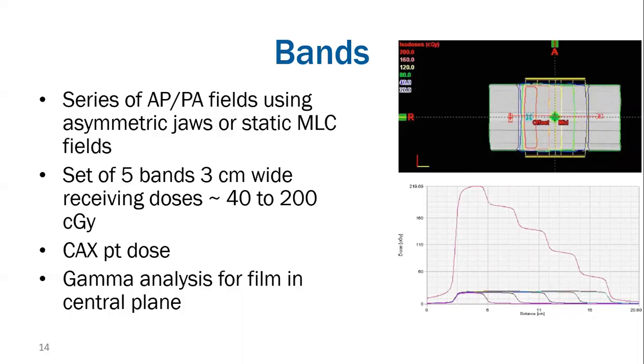So here, like I said, it's a series of AP/PA MLC defined fields using either the jaws or the static MLCs. It's a set of 5 bands, each of which are 3 centimeters wide, receiving doses from 200 to 40 centigray in kind of even increments. We then measure the central axis point dose, and we can perform gamma analysis for film in the central plane.